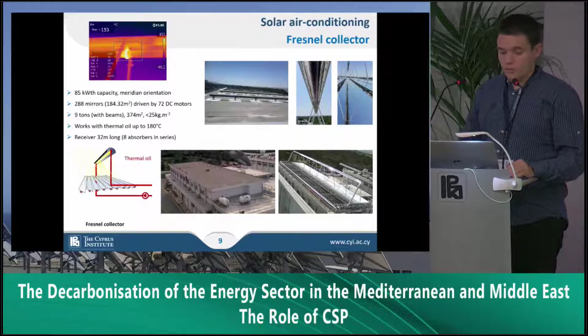It works with thermal oil up to 180 degrees, but this kind of collector, even small like this, can operate to much higher temperature, but for safety concerns, we limited ourselves to this temperature. The receiver is 32 meters long with 8 absorber tubes in series. The storage medium that we're using is very simple. It's simply water, that we can heat up to 146 degrees. This represents 2 hours of storage during the summer for cooling and 4 hours of heating during the winter.